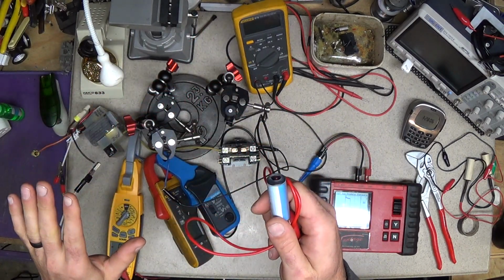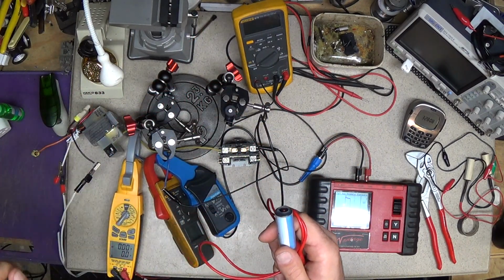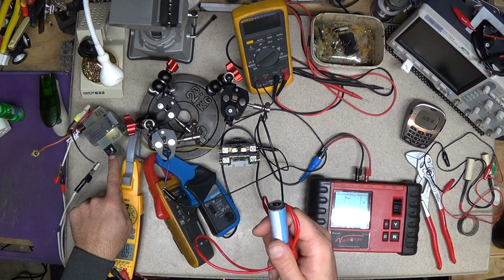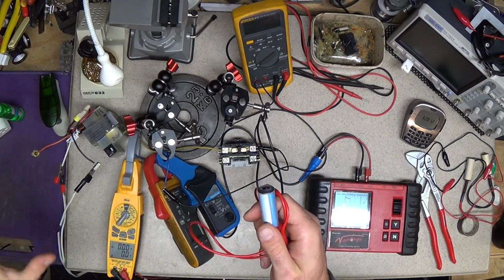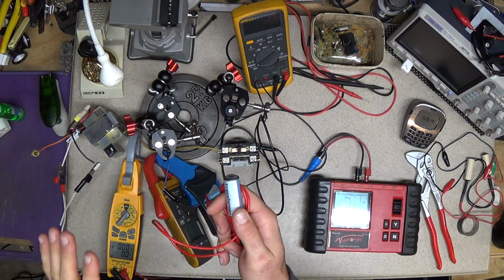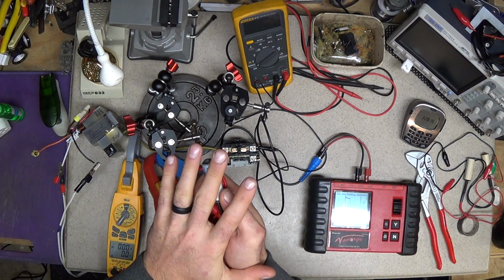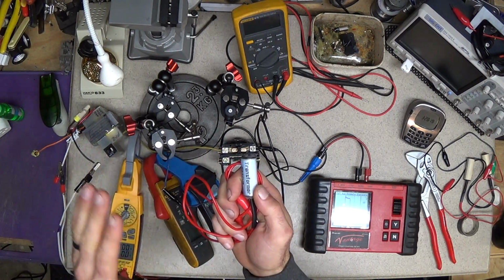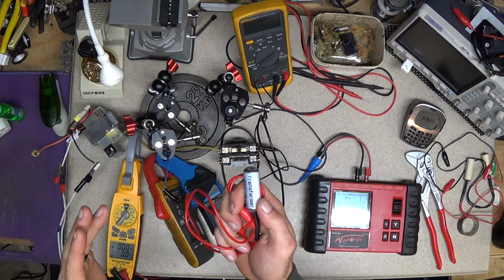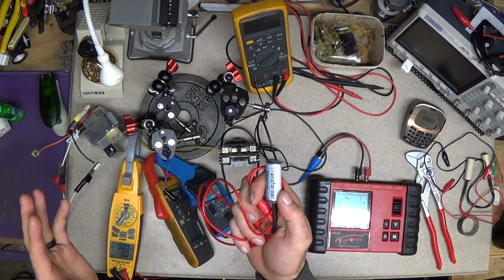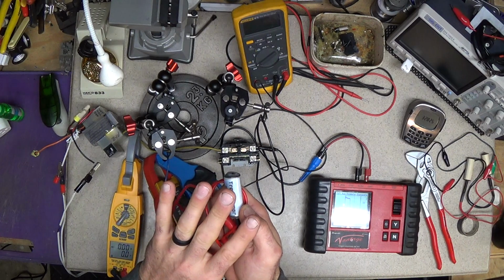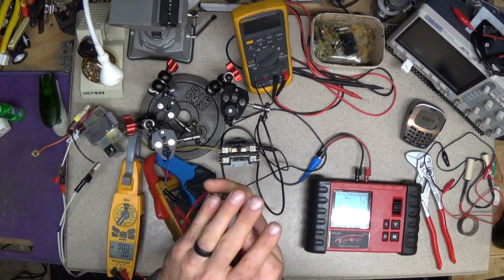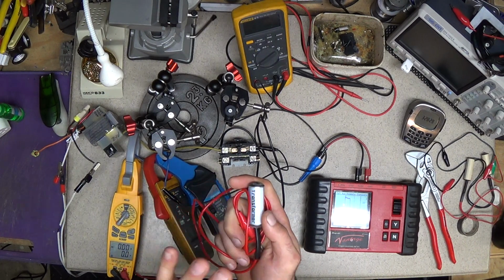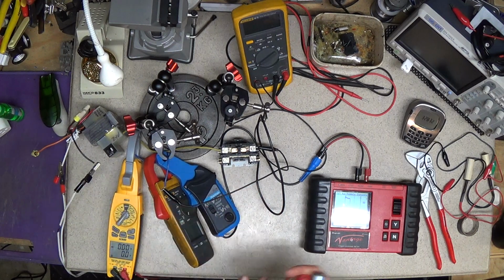Although the one thing is, this does lock it out, so it's not like constant resetting. But even in a case where this is constantly resetting, every half second or something weird like that, you can see that once this does start to get warm, you're not getting that 17 amp inrush.